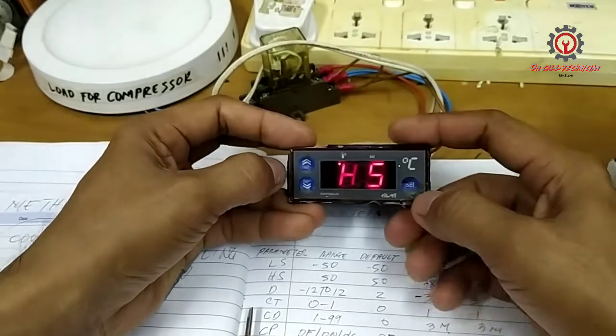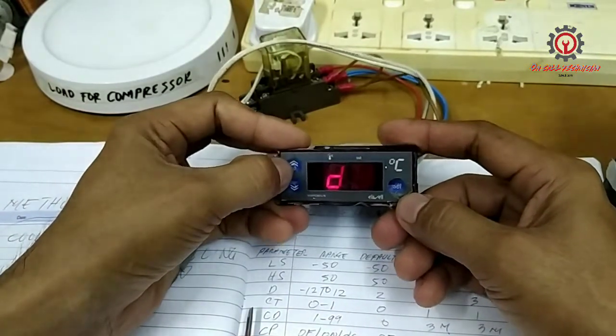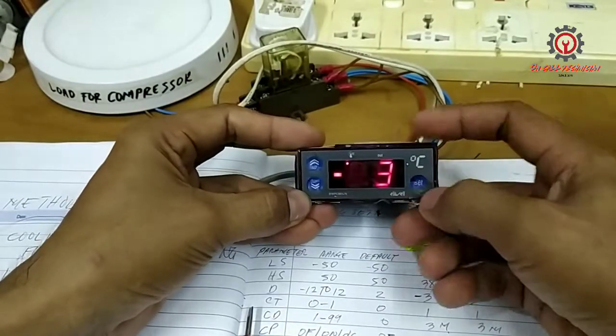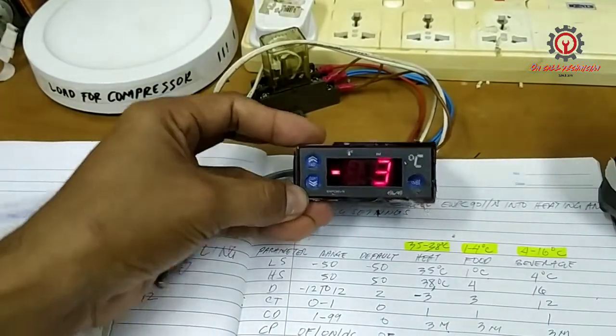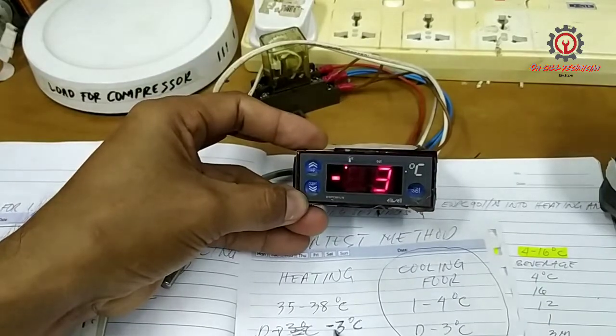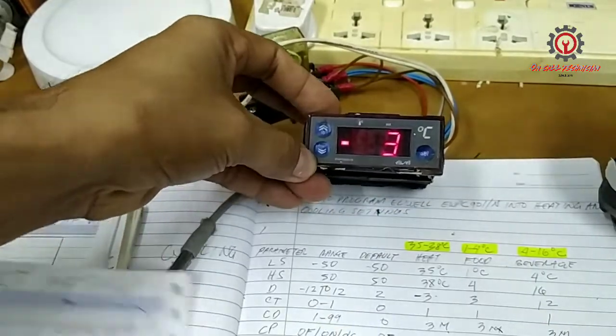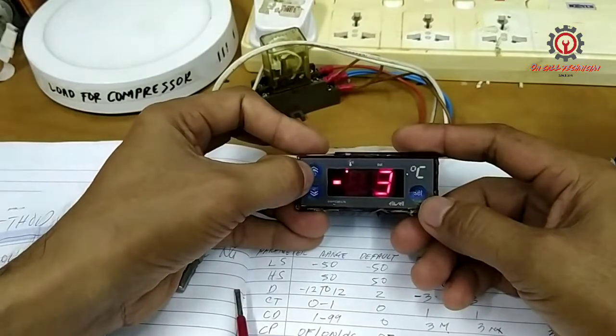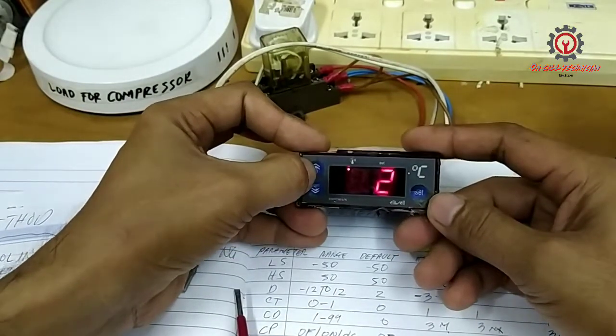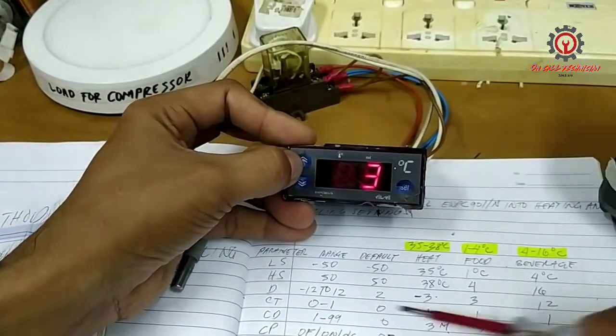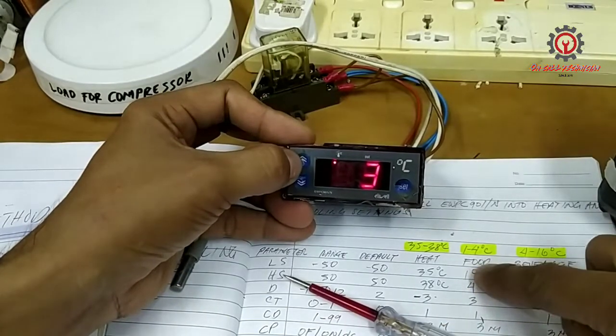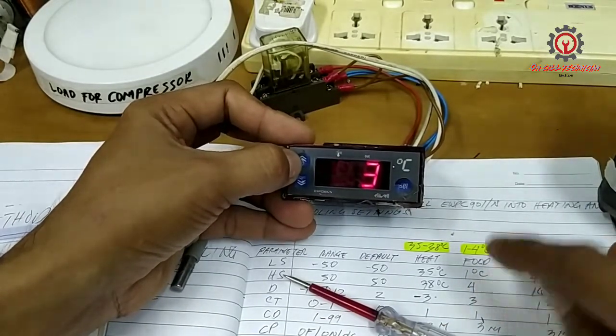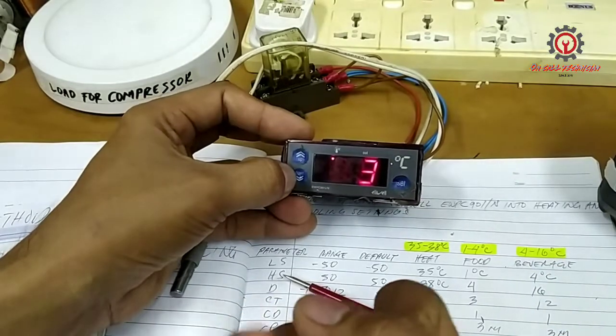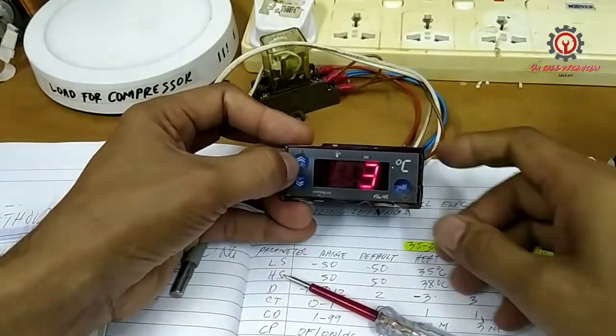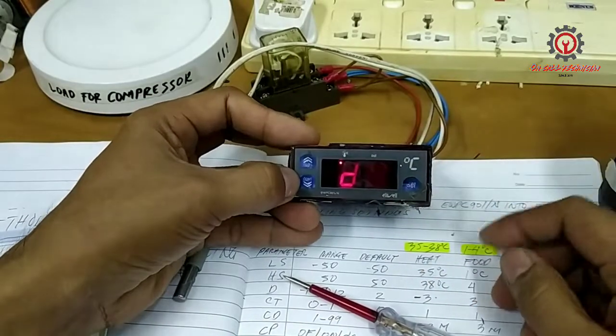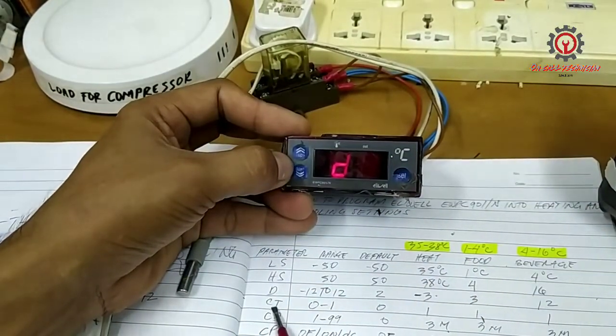This is the differential. Okay, set button, and last time I entered the -3 here because this was in heating. Now I'm going to change that to 3 because my LS is 1 and my HS is 4, so from 1, 2, 3, 4, so I have a 3 differential here. Just press set, and next, guys, is the CT.